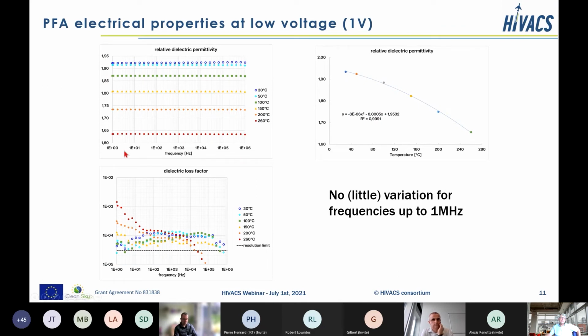Those are measurements in the frequency range up to 1 megahertz at different temperatures. And the measurements are done at low voltage, at 1 volt. And here we see that the dielectric permittivity doesn't change with frequency, but it changes with the temperature. It decreases with increasing temperature. And on the other hand, the dielectric loss factor, the tangent delta, is quite low, in the order of 10 to the power of -4, which means that we can neglect cable heating due to dielectric losses.